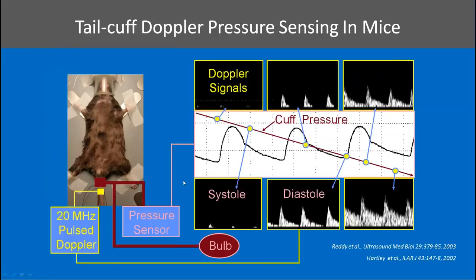The last application is the tail cuff Doppler measurement. A cuff probe is placed on the tail along with a pressure cuff, and we can measure blood pressure non-invasively. This has been validated with simultaneous invasive pressure measurements. As the pressure in the tail cuff drops, flow starts to appear — where it first appears is called systolic pressure, and where it becomes continuous is called diastolic pressure. This is an additional option for those who have the system.